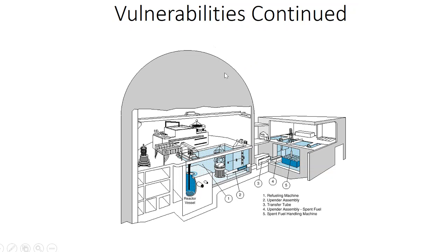Here we have a cross-sectional view of what appears to be a pressurized water reactor containment and its auxiliary building housing the spent fuel pool. Now this is important to bring up because any licensed reactor operator, which I imagine there are a few of watching this presentation, can tell you when you're at mid-loop in a refueling outage, your time to boil drops substantially. We'll be taking fuel out here, putting it through the transfer canal, and moving it into the spent fuel pool. This is a highly dynamic situation, and the time to boil in all of these places changes multiple times with each fuel move.